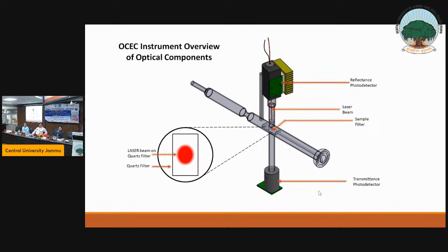So you sometimes hear a subset of thermal optical analysis called TOR, which means thermal optical by reflectance. And then you have a transmittance detector at the bottom, which measures the intensity of the laser as it passes through the filter. That's thermal optical analysis by transmittance, or TOT. There are various methods that people have developed, and some use reflectance, some use transmittance.